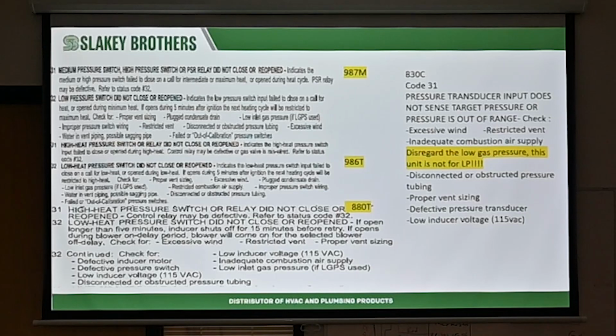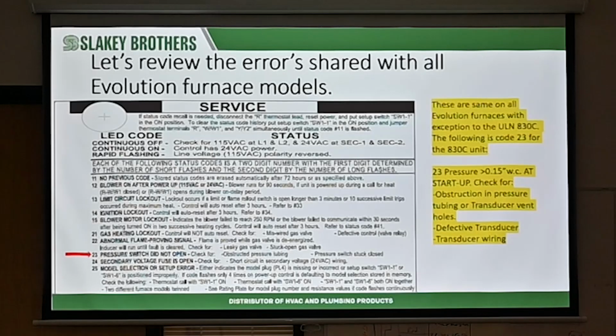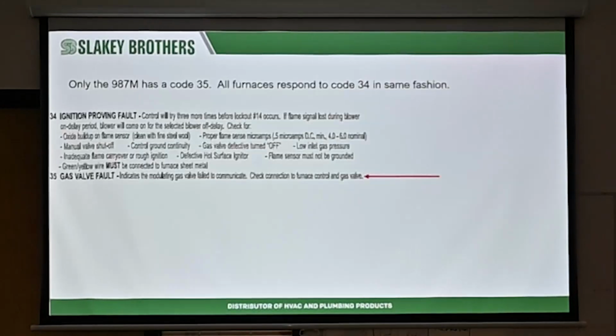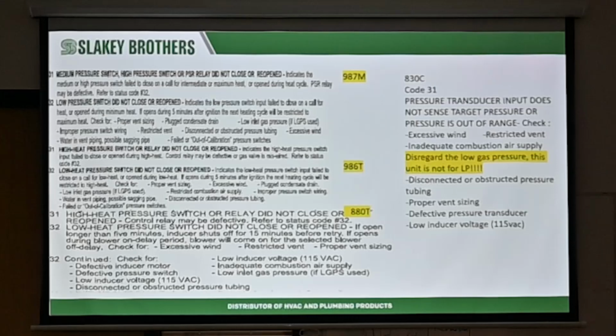So this is easy because we've got a furnace to go over, but you can go sheet metal because of the grounded wire. A lot of times I go sheet metal, I'll put my probe in here in the sheet metal. You check one point, I got 24 volts. You check the other point, I got 24 volts. My inducer's off, my pressure switch is closed. It shouldn't be. My pressure switch is faulty. You can undo the hose. Or I should have, oops, I kept pressing this thing. What we're looking for, did not reopen, means that that switch is closed. So that's what we're going to check.